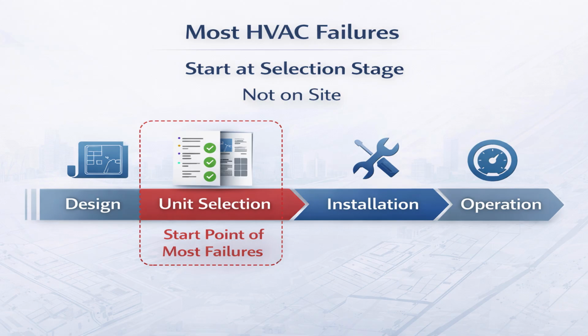They start when we rely too heavily on catalog data without fully questioning the assumptions behind it. When safety margins are added without really understanding what they are compensating for, and when numbers are accepted but behavior is not analyzed. At that stage, nothing looks wrong. The unit appears adequate, the selection sheet looks complete, and the submittal gets approved. But once the unit is installed and the system is operational, those early assumptions begin to show their impact. And by then, the room to correct the problem becomes very limited. Changes are costly, retrofits are difficult, and what was once a small selection decision turns into a long-term performance issue. This is why understanding where failures truly originate is so critical for engineers.